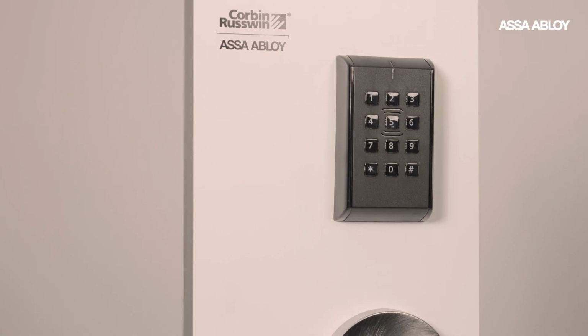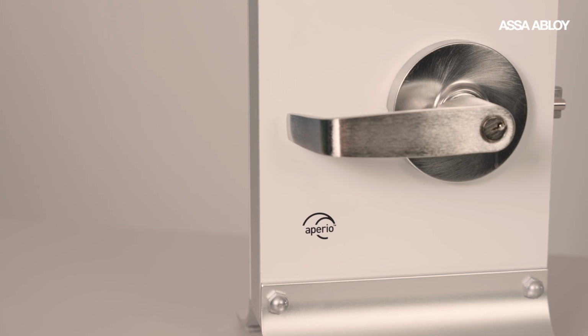So how does the Aperio actually get back to the controller? So what it does is it connects wirelessly to the hub, and then the hub connects to the EAC panel. And where's the hub installed? It's about 80 feet from the lock, give or take, and then the hub will be connected either in the ceiling or on the wall. And what's the ratio of locks to hubs in general? Depending on what you're utilizing for the access control software, it will either be 1:8, 1:16, or 1:64.